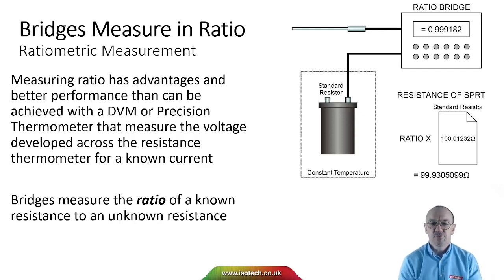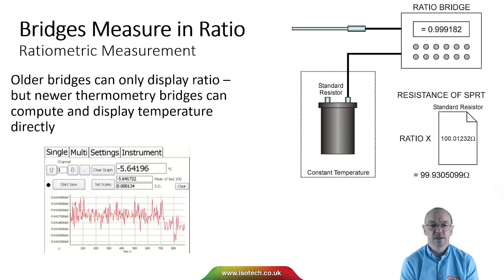So, as I said, measuring ratio has advantages. We can get better performance than can be achieved with a DVM or precision thermometer that measure the voltage developed across the resistance for a known current. Bridges measure this ratio. So we have a standard resistor, and we might keep that at a constant temperature to have a calibration certificate, and we can compare the unknown resistance of the SPRT to the known resistance of the standard resistor. And then if we measure the ratio, multiply that by the resistance value of the standard resistor, we get the resistance of the SPRT.